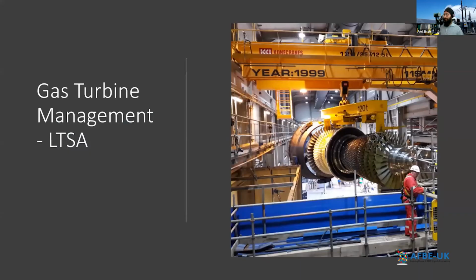We've got a very good partner in Siemens for our gas turbines. We have a lifetime service agreement with them that allows us to perform minor inspection activities, hot gas path inspections, and major activities with Siemens on a periodic basis. For us, a minor is every 8,300 hours, and a hot gas path inspection is three times that frequency. We also carry out major lifetime extensions at the station.